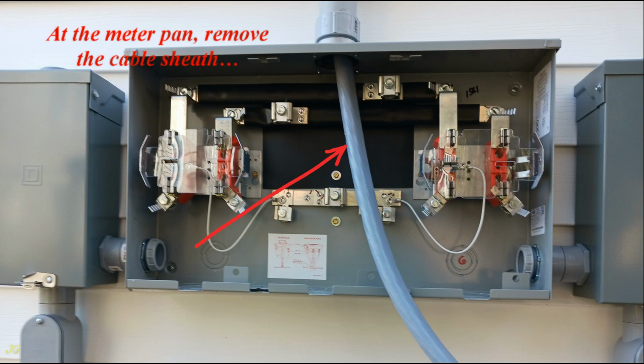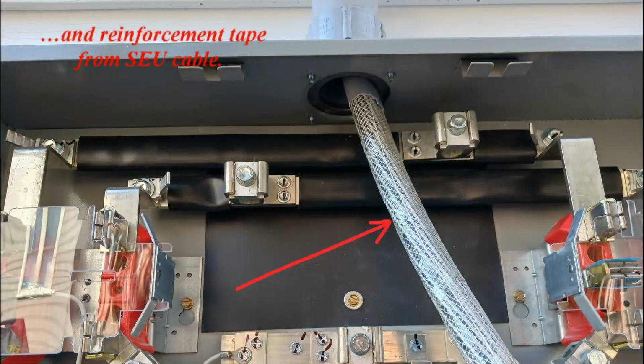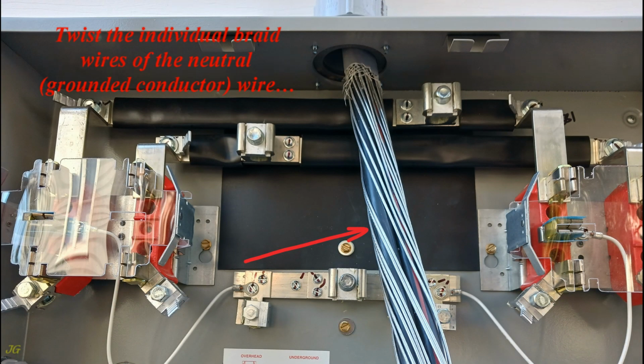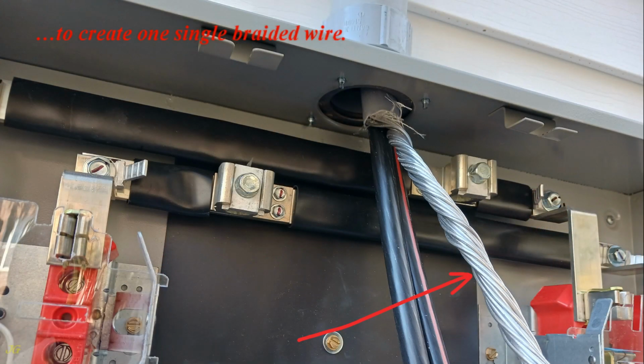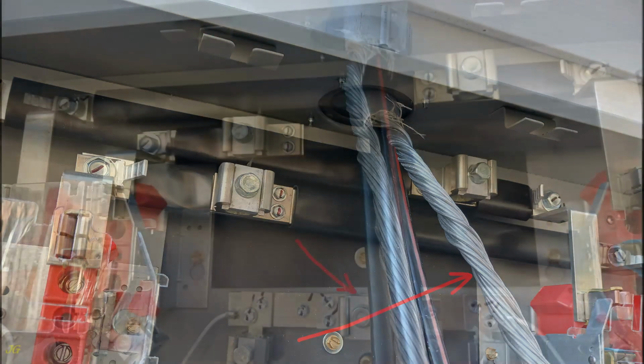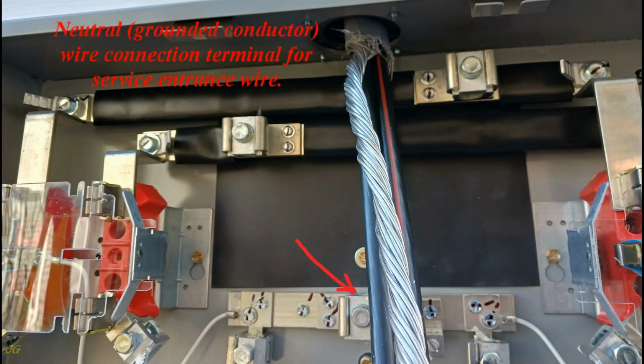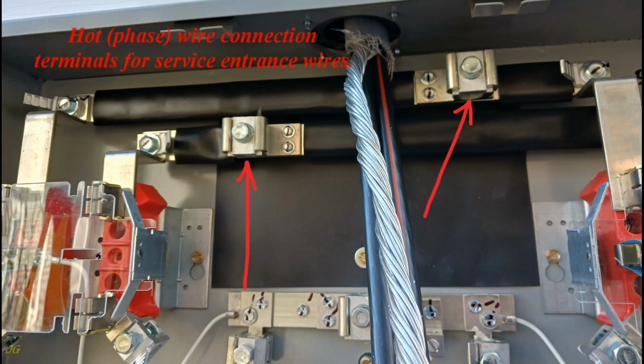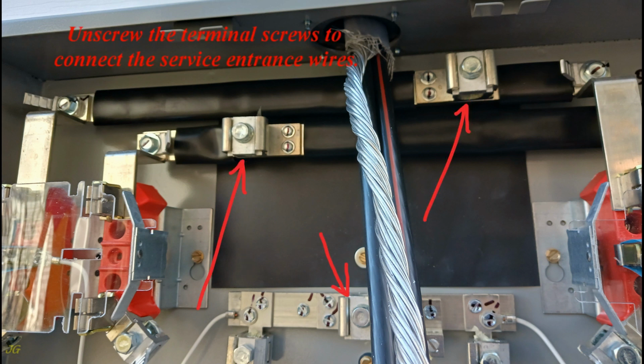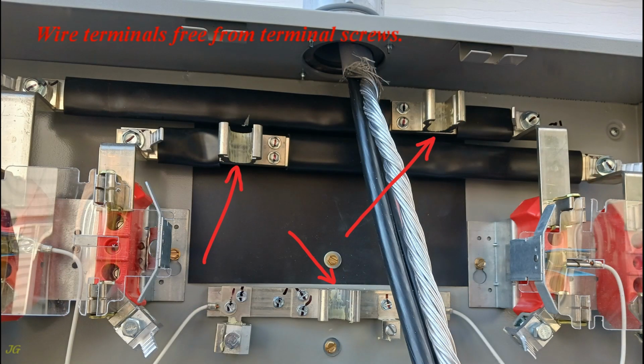At the meter pan, remove the cable sheath and reinforcement tape from the SEU cable. Twist the individual braid wires of the neutral, grounded conductor wire to create one single braided wire. Neutral, grounded conductor, wire connection terminal for service entrance wire. Hot, phase wire connection terminals for service entrance wires. Unscrew the terminal screws to connect the service entrance wires. Wire terminals free from terminal screws.